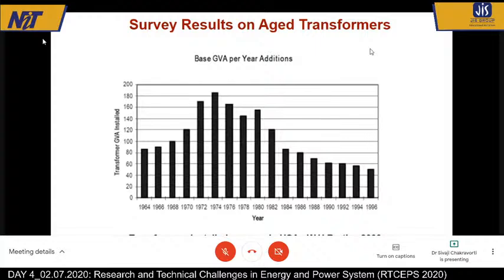The solution is that we have to first test this transformer. Here I am talking about real life tests, nothing to do with simulation. We have to do real tests and find out the condition of these transformers. If it is good, we will not do anything, let them run. If we find that one or two transformers are in bad condition, then those will definitely be replaced. This is the policy followed nowadays, not only in India, but all over the world.